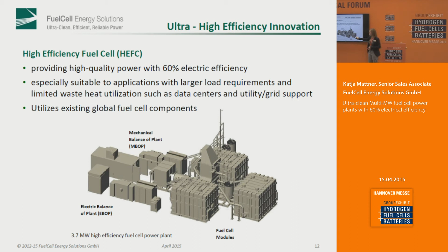So the advantages here of the high efficiency fuel cell: this is the standard configuration I mentioned before, 2.8 megawatts with 47% electrical efficiency. We already had a development to increase the electrical efficiency to 58% with the turbine, but we noticed it's better for us to leverage our proven DFC fuel cell technology, using only one technology to reach 60%, as it's proven worldwide and in operation worldwide, achieving higher efficiency. Also, we need 20 to 30% less water compared to the DFC turbine, and it has a smaller footprint and lower installation costs.